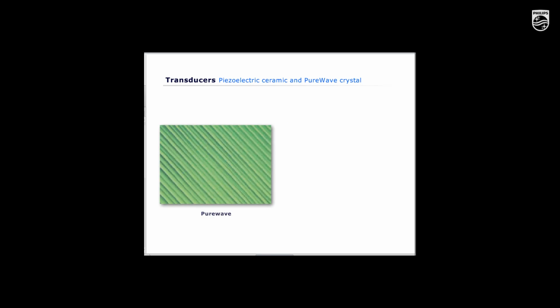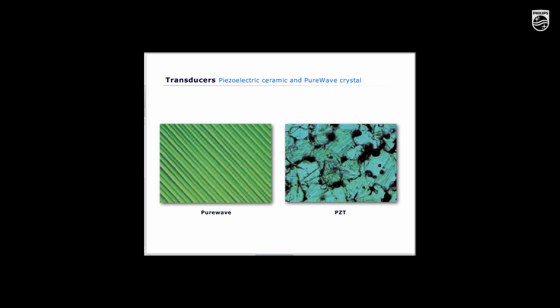A variety of ceramic piezoelectric materials are used to create the ultrasound transducers. One of the most popular is PZT, or lead zirconate titanate ceramic, where the fine powders of the component metal oxides are mixed and then heated to form a uniform powder. The powder is mixed with an organic binder and baked into a dense polycrystalline structure. Notice that the texture is not perfect, as you can see on the right. New research has resulted in the development of other types of materials that also present good characteristics for ultrasound imaging. One example is the Philips PureWave element, which you can see on the left side.